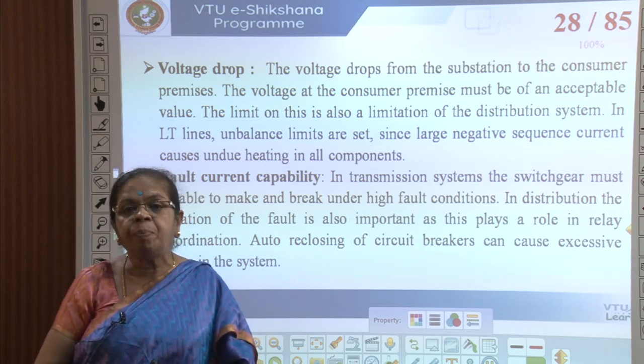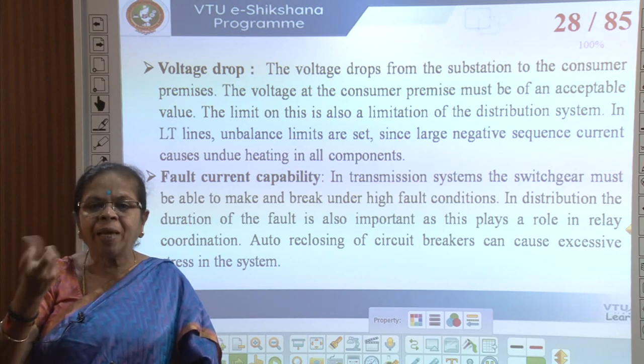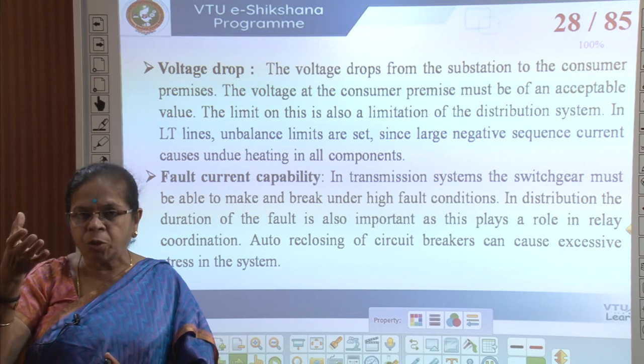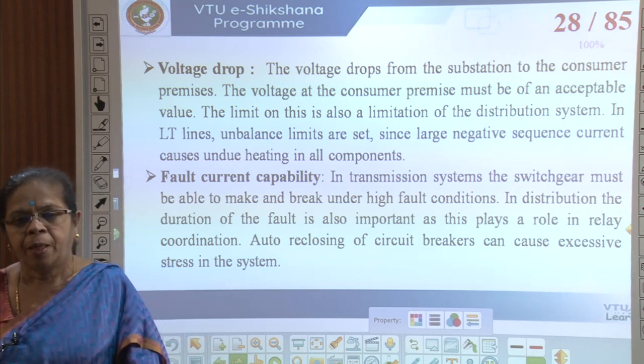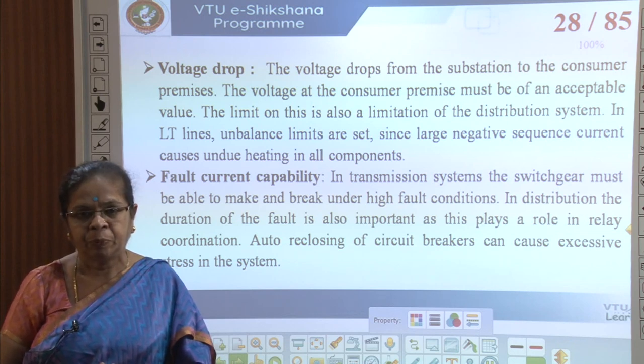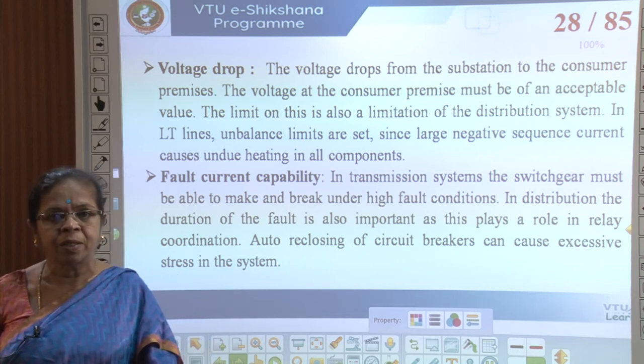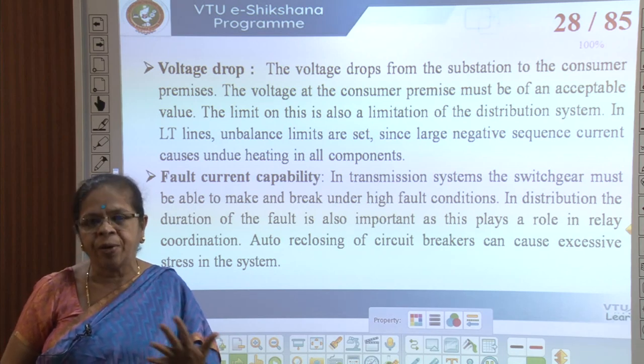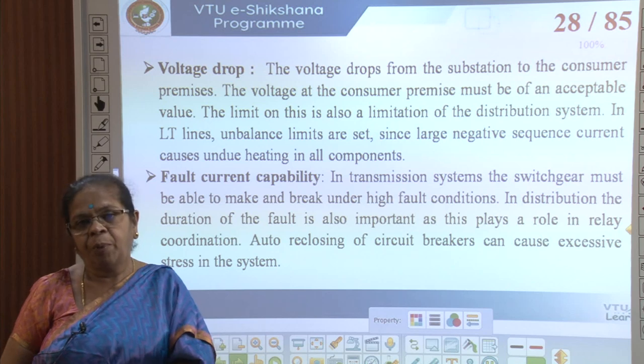Then there is fault current capability. The switchgear must be able to make and break the fault; before it breaks, fault current will be flowing for a short time, so distribution lines and switchgear must be able to bear this current for a very short duration. Modern circuit breakers are equipped with auto-reclosure facility, but this can cause excessive stress in the circuit breakers. Though auto-reclosure improves system reliability, it creates a lot of stress — the breaker may close on a fault if the fault has not cleared when the breaker recloses.